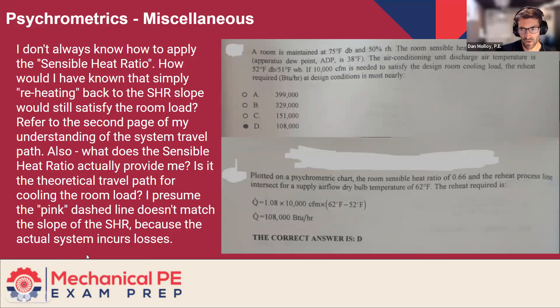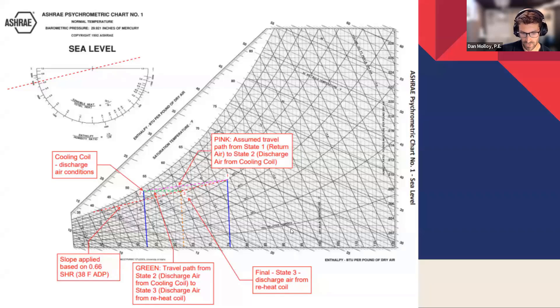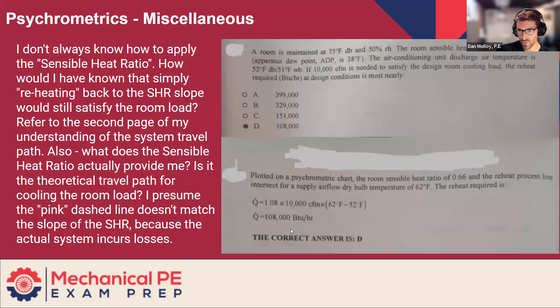Really good question about a common problem that comes up. I'm actually going to read this problem out and then I'm going to jump over to the really nice drawing that you did on the psychrometric chart. We'll spend a couple of minutes on this. So the question is, a room is maintained at 75 degrees and 50% RH. The room sensible heat ratio is 0.66. The apparatus dew point is 38 degrees. The air conditioning unit discharge air temperature is 52 degrees dry bulb, 51 degrees wet bulb. If 10,000 CFM is needed to satisfy the design room cooling load, the reheat required in BTUs per hour at design conditions is most nearly what?